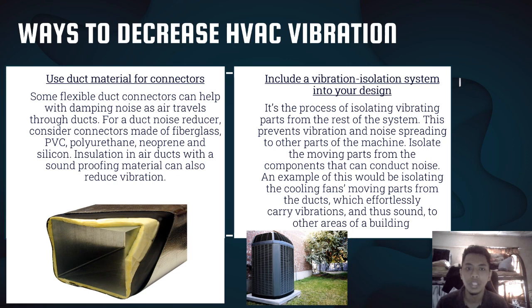So, ways to decrease HVAC vibration. First, we can use material for duct connectors. Some flexible duct connectors can help with damping noise as air travels through the duct. For a duct noise reducer, consider connectors made of fiberglass, PVC, polyurethane, neoprene, and silicone. Insulating the air duct with a soundproofing material can also reduce vibration.